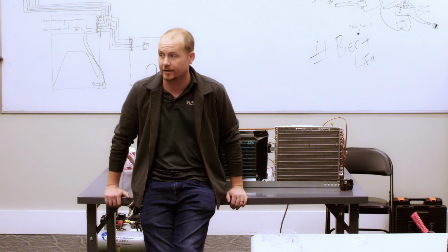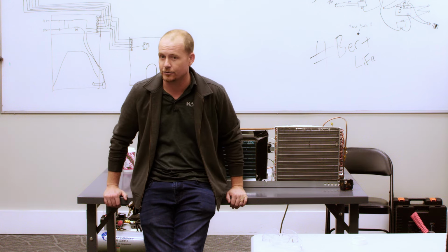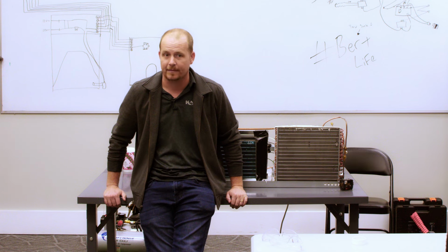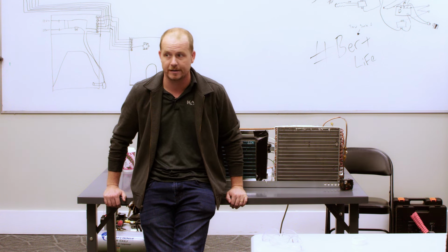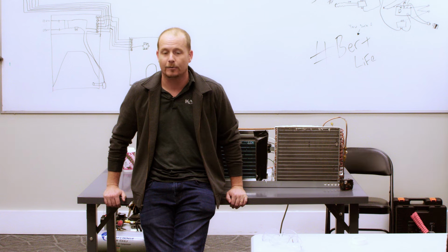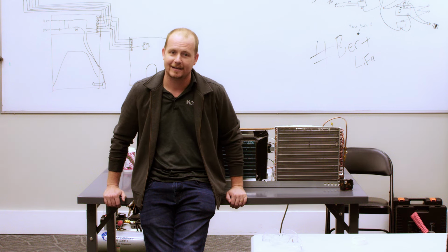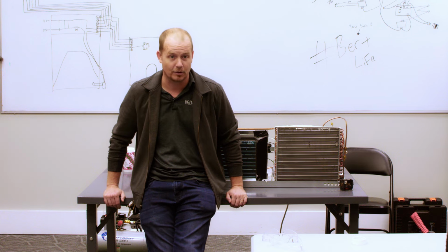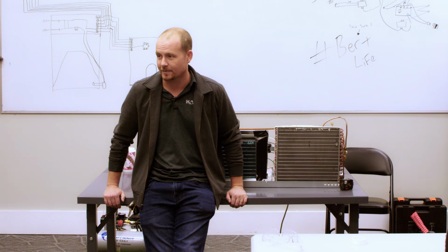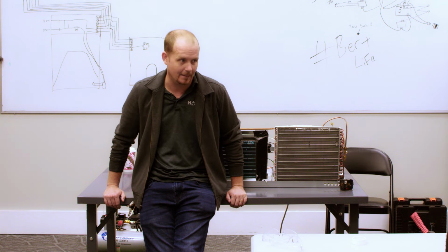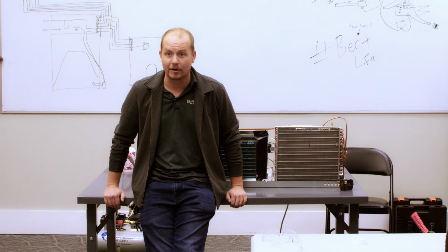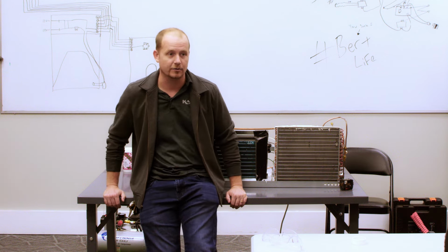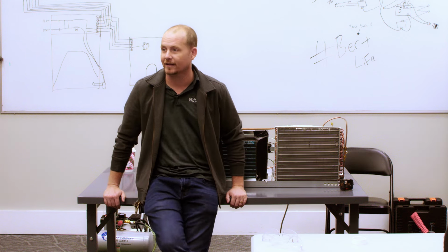And this is why you'll notice, you'll hit a point as you start charging a system that head pressure will start going up pretty darn quick. Now, when you're dealing with ductless systems, you're going to hit a safety state where it actually starts limiting its compression, and that tricks you because your head pressure doesn't just keep going up. We've run into that before, which is again why you have to use scales and you have to weigh it in and all that kind of stuff.